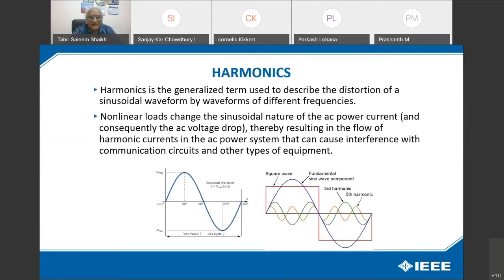Harmonic is a generalized term used to describe the distortion of a sinusoidal waveform by waveforms of different frequencies. Non-linear load changes the sinusoidal nature of the AC power current and consequently the AC voltage drop, thereby resulting in the flow of harmonic current in the AC power system that can cause interference with the communication circuits and other types of equipment. So this diagram shows a waveform disturbed by harmonics; the harmonics will create frequencies that are multiples of the base frequency.